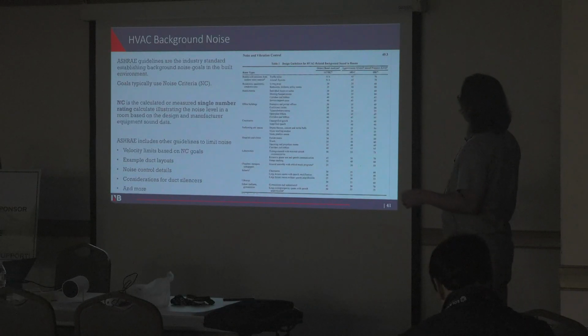This is ASHRAE Chapter 49, and Table 1 is a list of spaces with dBA and dBC values, but the NC category is right here. You can see hotel room 30, office building conference room 30, teleconferencing 25, open office 40, hospitality and clinics patient room 30, wards 35, operating procedure room 35, corridors and lobbies 40.